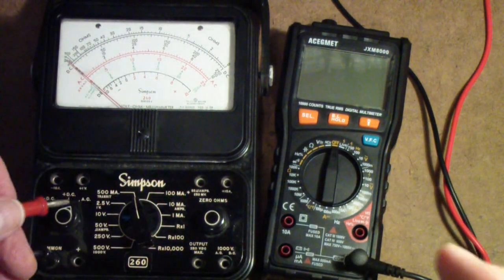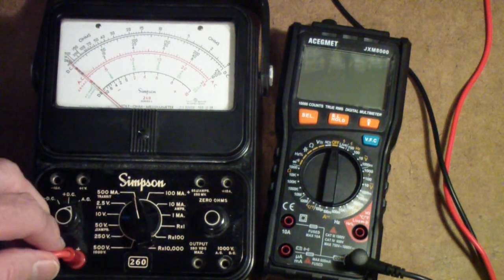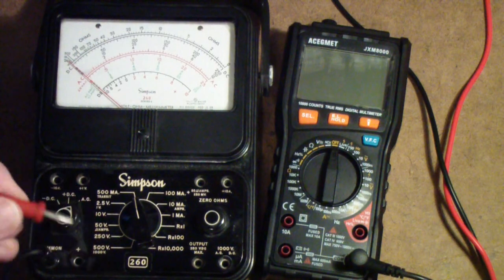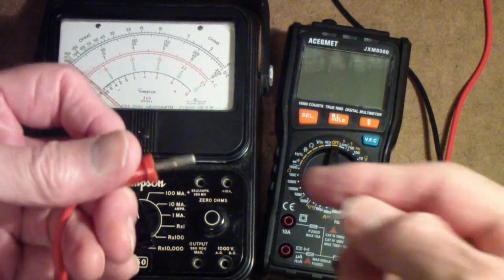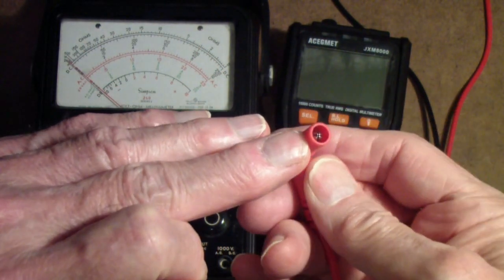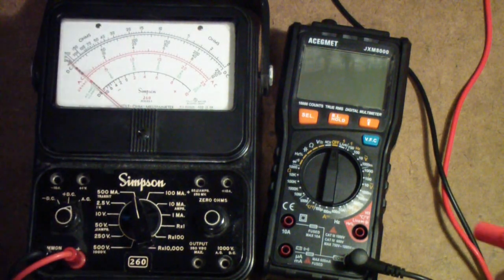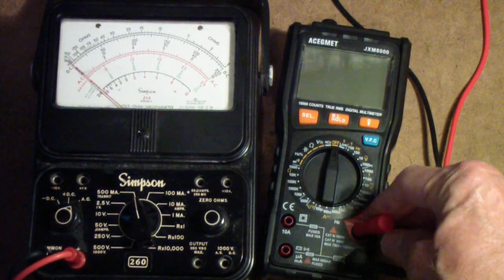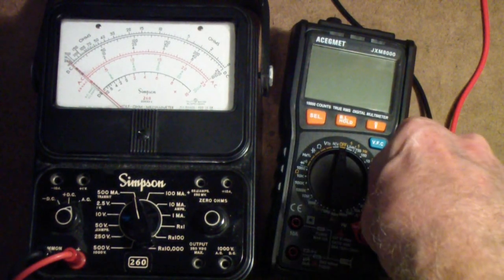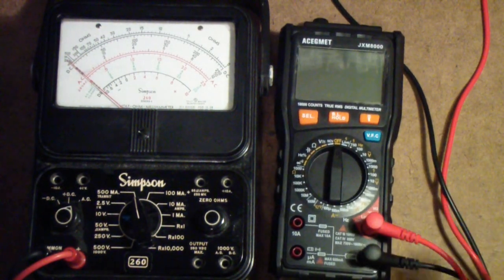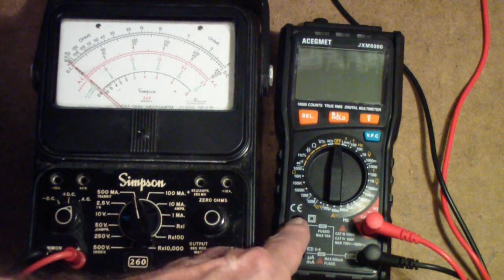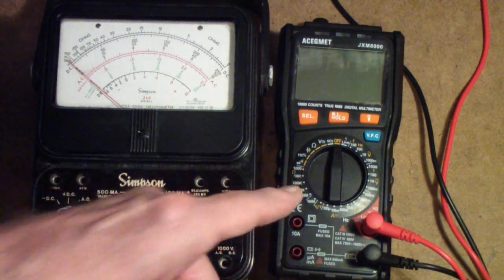The main reason they changed the probe style is there was a problem with people connecting the test leads to AC and then unplugging or never plugging in the other end of the test probe and then coming in contact with the test probe. So they put this what's called a sheathed connector around it. One reason that I point that out is these meters and many good modern multimeters sense where you have probes plugged in. For example, if you don't have a probe plugged into the proper current position, it won't let you measure current.